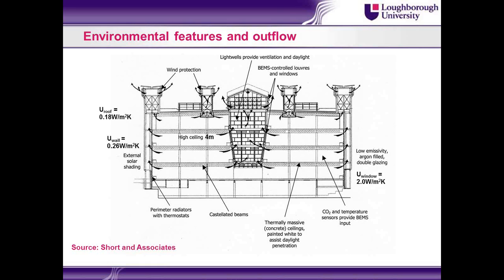I always talk about the outflow first, because if you remember from my earlier slide, it's the air leaving the space that drives this flow. Buoyancy-driven natural ventilation is not air coming in and pushing stale air out. It's air leaving the building, sucking fresh air in. That's how this ventilation flow works.